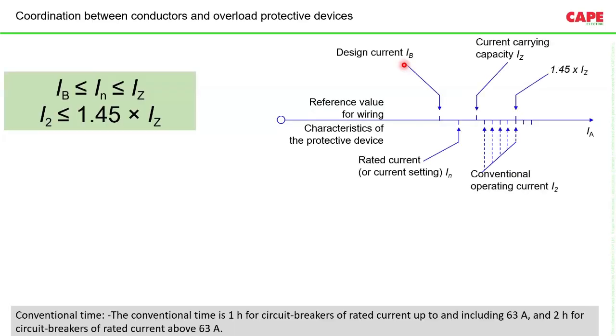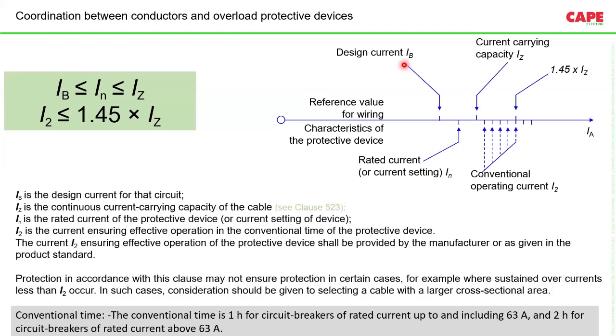When we select an MCB for a typical application, please be sure that it is not just a case of thinking that today I need 10 amps current and tomorrow I may increase it to 60, so right now let me use a 63 amps MCB. This is a wrong idea. The correct way of using protective devices: first of all, the protective device is to protect the circuit. In order to protect the circuit, the first item on the circuit is the wire, so the device should be selected based on the wire size.